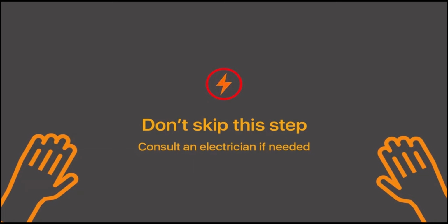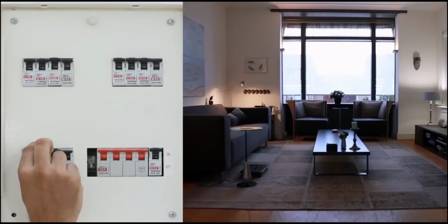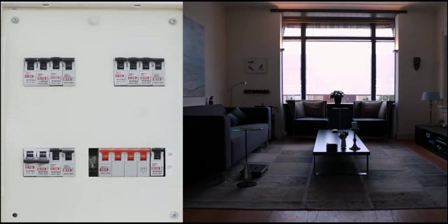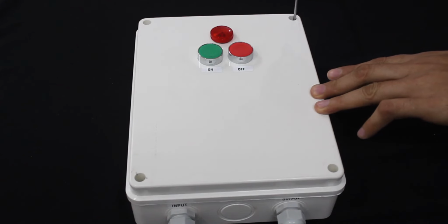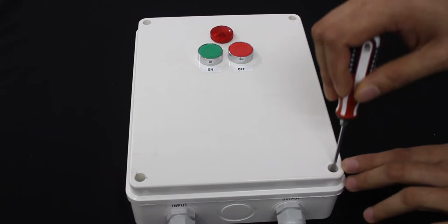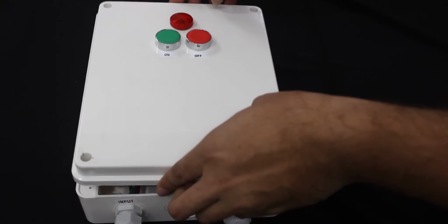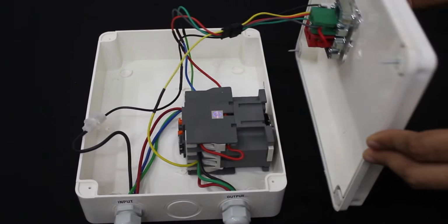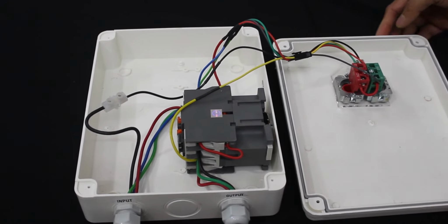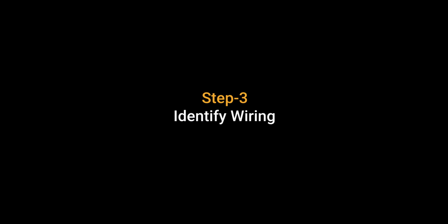To start off with, go to your MCB panel, identify the circuit breaker connected to the motor panel and turn them off. If your breakers aren't labeled, turn off the main supply. Now let's get to step 2. Open the motor panel. Now that your power is off, you can safely open the motor panel using a screwdriver. Alright, now that the motor panel is open, let's get to step 3, identifying all the wires in it.